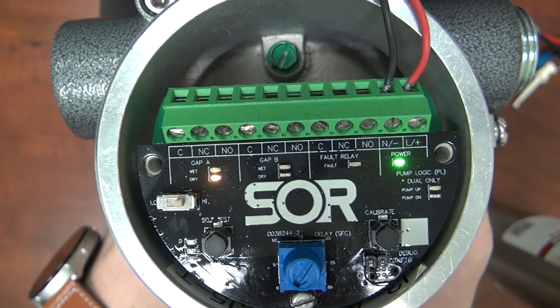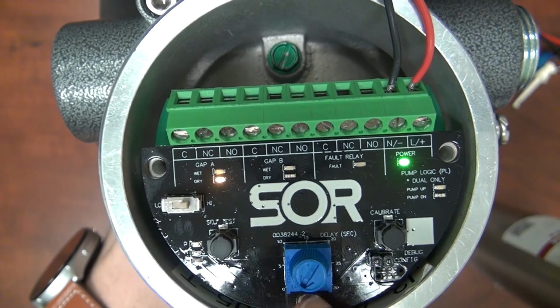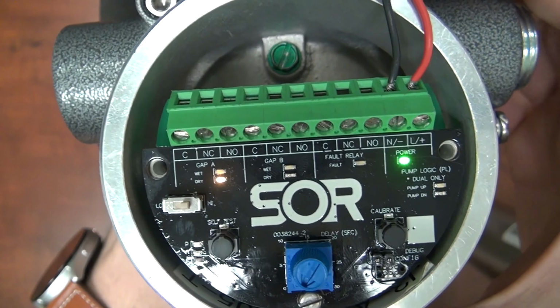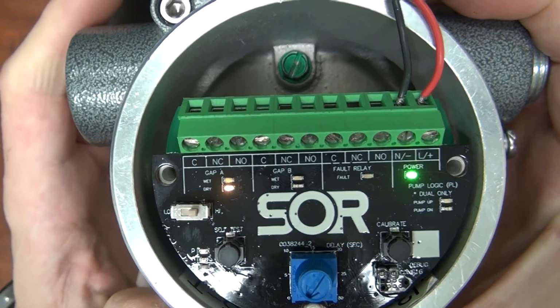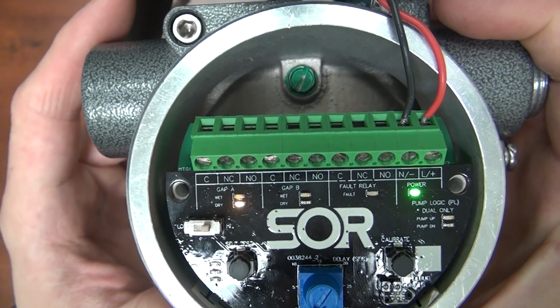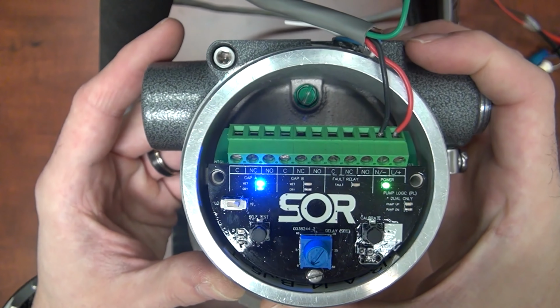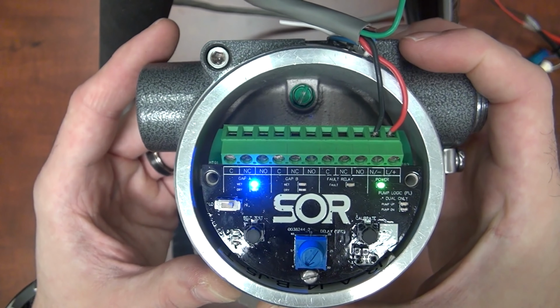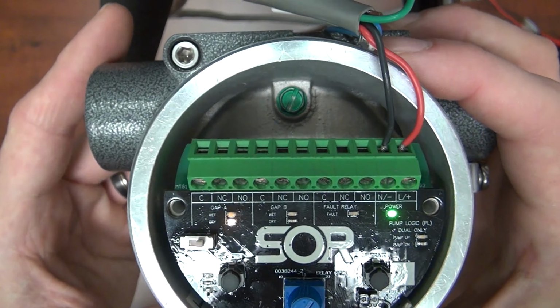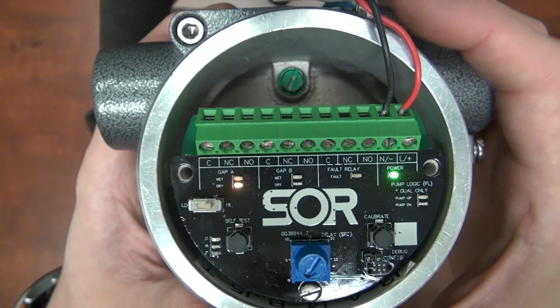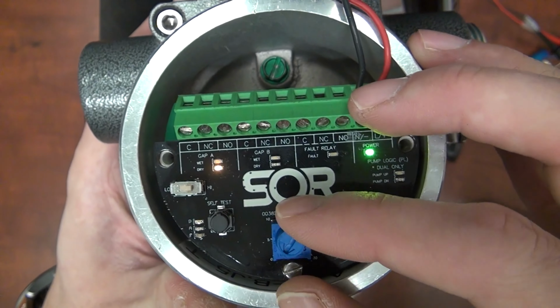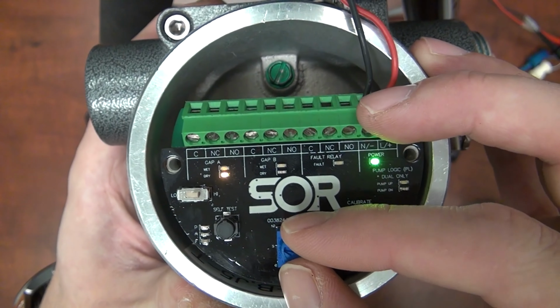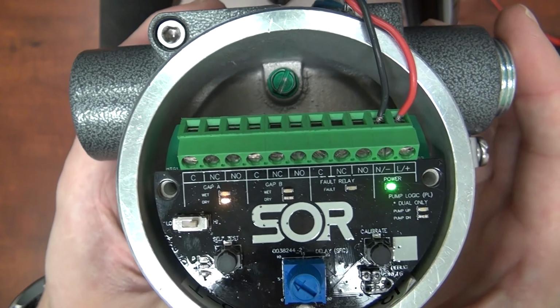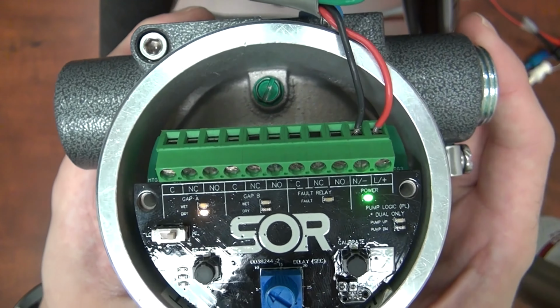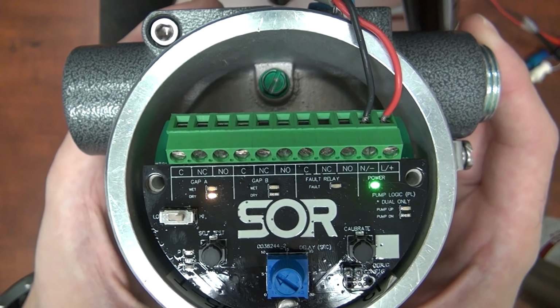Next, let's demonstrate the time delay feature. Currently I have it set to the 0 or off position. When I lower the probe into the water, it will actuate immediately. Removing it will deactuate immediately. If I turn the time delay somewhere to the middle, around 5, 10, 15 seconds, and put it in the water again, we will see when it detects liquid in the gap, the LED will begin flashing.